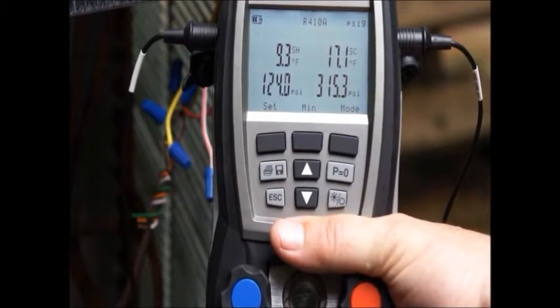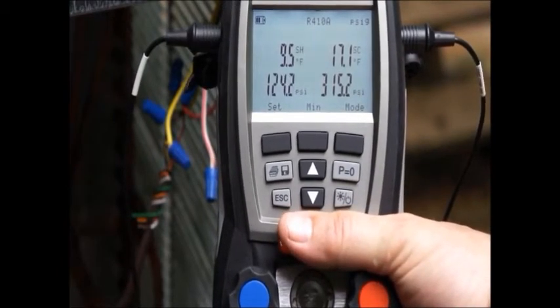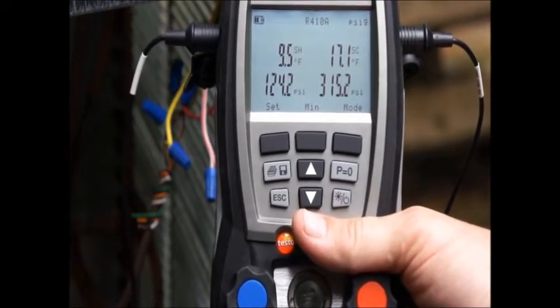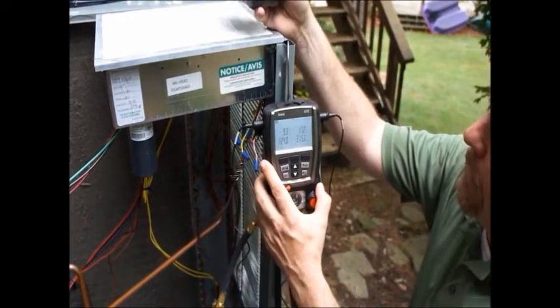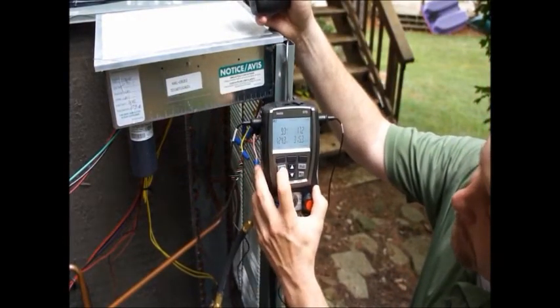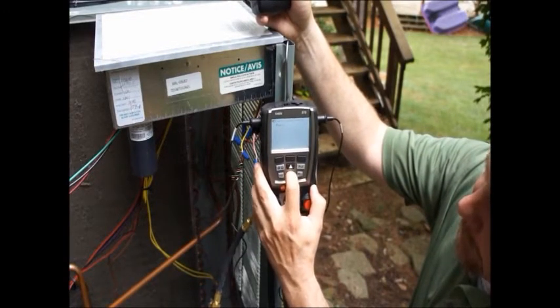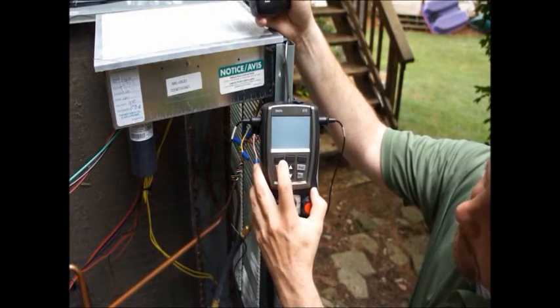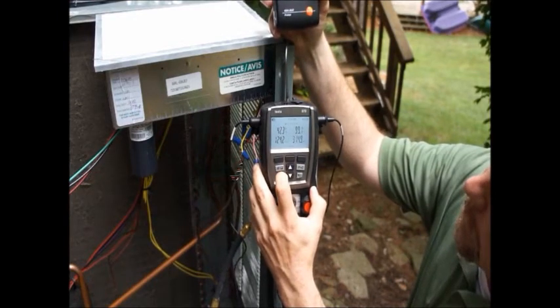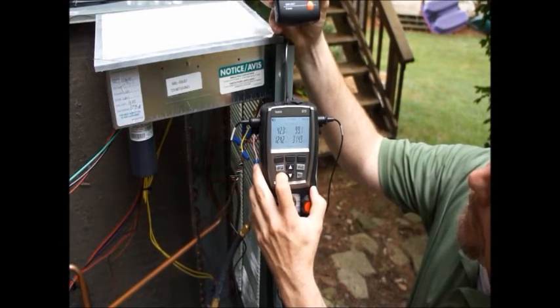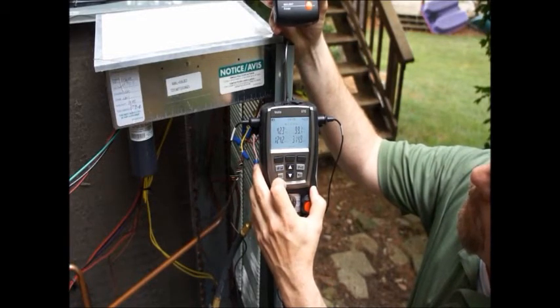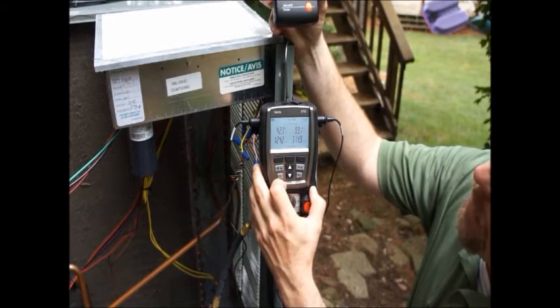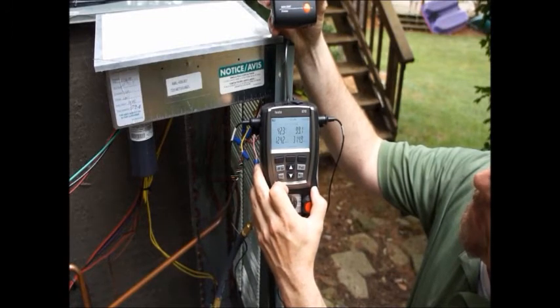That's our basic initial walk through of the menus and there's a couple other cool things I want to show you. One of the cool things with this instrument is it allows us to print. If I hit the print key, go down to signal measurement and hit OK, scroll down to print and hit OK, it's going to shoot a signal out via IR to the printer and print out the unit model number, serial number, firmware version, the pressures, temperatures, superheat and subcooling.